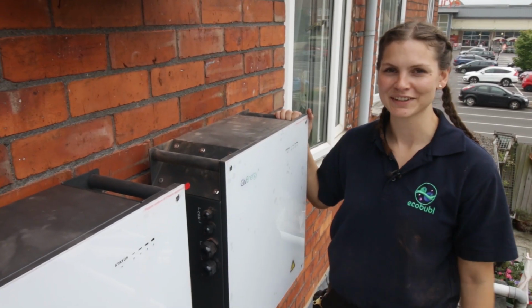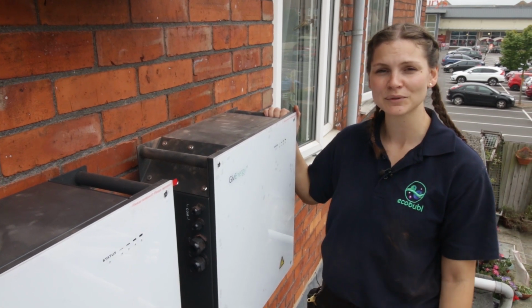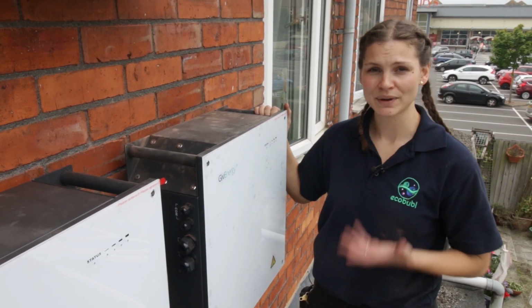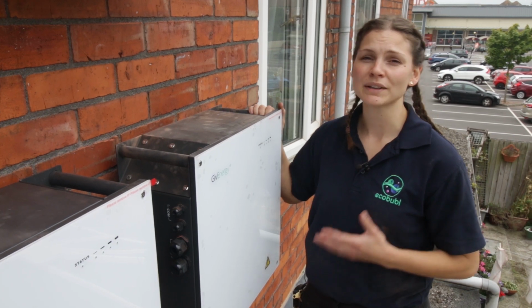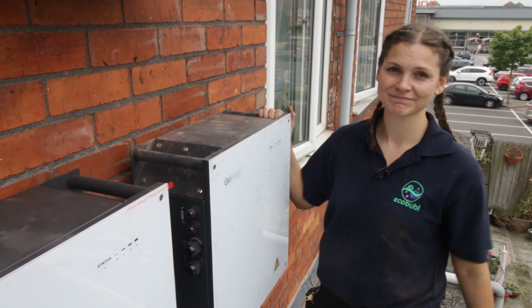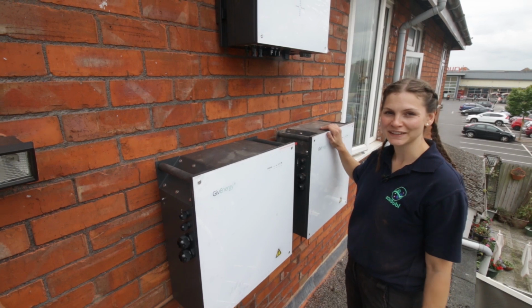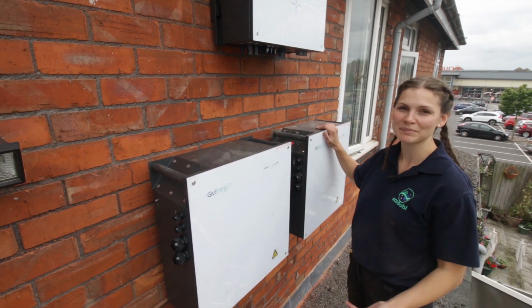All GivEnergy hybrid inverters are IP65 rated, so can be installed outdoors. They also rely on natural air convection to keep the system cool. That's why it's so important to get those clearances correct. So now we've got the inverter and the 2 batteries fitted, it's time to get them connected to the PV and the main power supply.